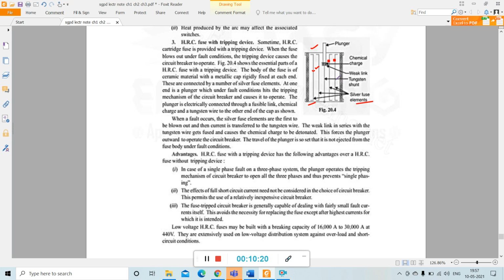There is a plunger which under fault condition hits the tripping mechanism of the circuit breaker and causes it to operate. So this is a plunger connected to one end, and this is a tungsten wire connected in shunt with the other end of the element, and there is a weak link. Inside this, a chemical charge occurs, which trips the plunger. The plunger is electrically connected through a fusible link, chemical charge and a tungsten wire to the other end of the cap. So when a fault occurs, the silver fuse elements are the first to be blown out, and then current is transferred to the tungsten wire, because the silver fuse element has a lower resistance compared to the tungsten element. The weak link in series with the tungsten wire gets fused and causes the chemical charge to be detonated.